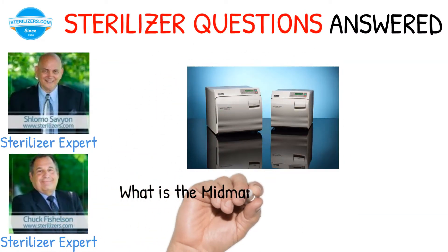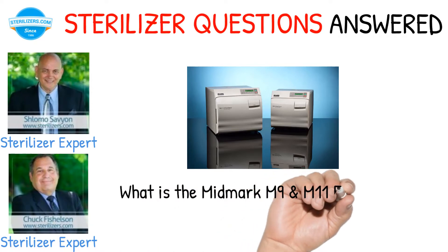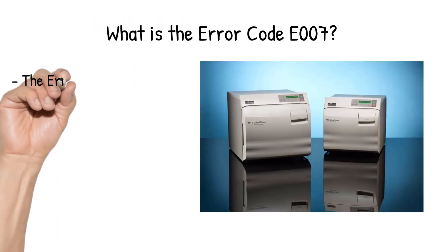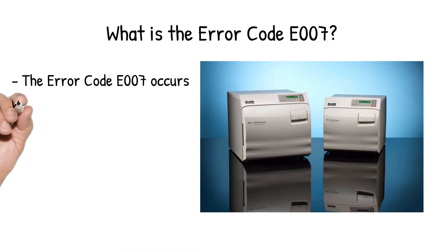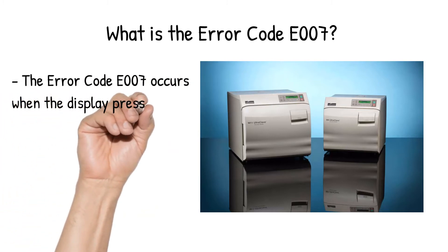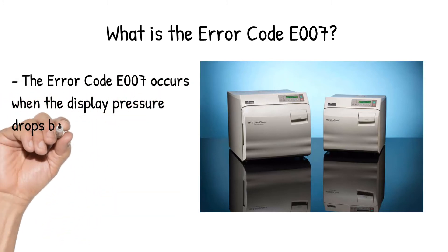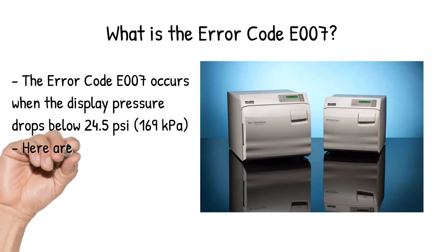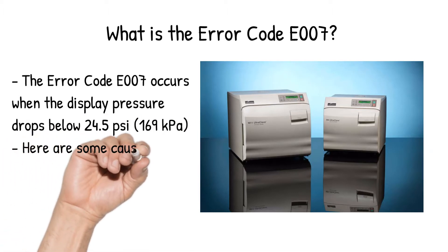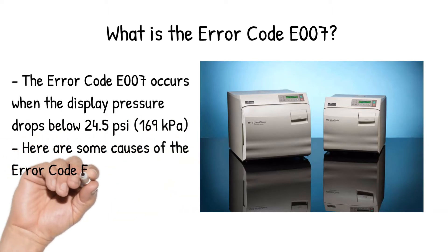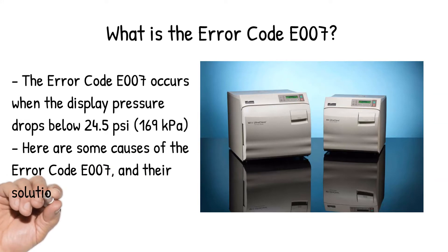What is the Midmark M9 and M11 Error Code E007? The error code E007 occurs when the display pressure drops below 24.5 pounds per square inch, 169 kilopascals. Here are some causes of the error code E007 and their solutions.